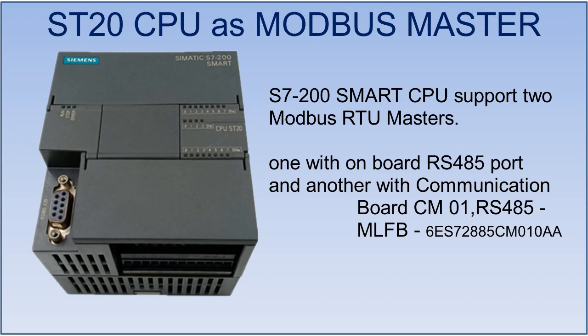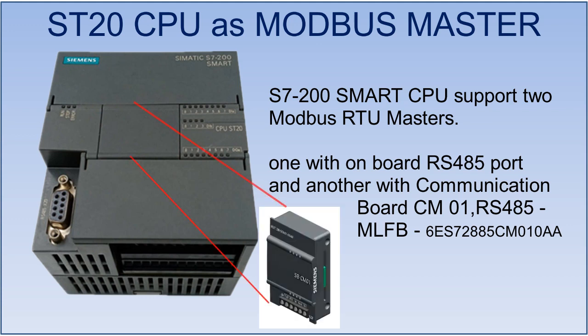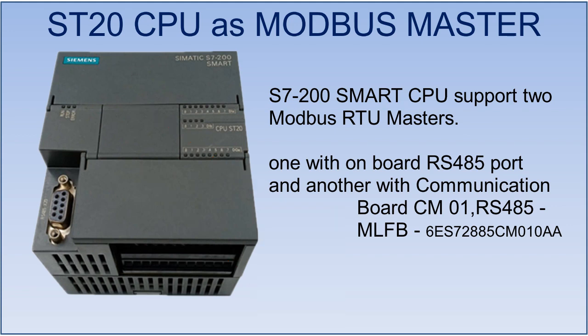The S7-200 Smart CPU supports two Modbus RTU Masters at a time: one with the onboard RS-485 port and another with communication board CM-01. That means you can communicate over two different slave networks or daisy chains at a time.